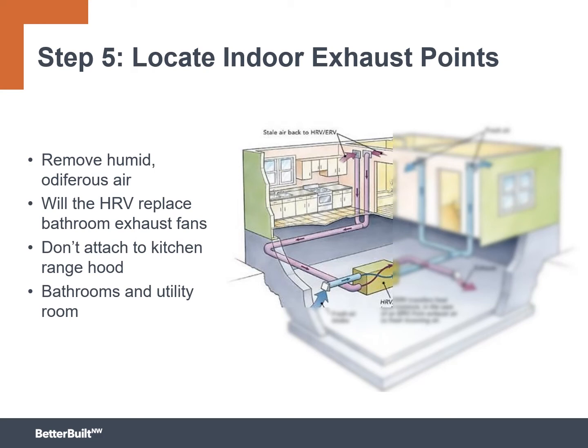But again, I keep using this word displace, right? So in this case, if we want to move, say, 10 or 15 CFM out of that bathroom more or less continuously, and by the way, there are some things like defrost cycles that have to happen with pieces of equipment where they temporarily maybe only recirculate air, so that's another consideration. But we can take a look and say the best case scenario might be we could put in a 70 CFM bathroom fan instead of a higher one. And that's going to meet 88% of the local exhaust requirement all by itself. And then the HRV exhaust will do the rest. So this may still give builders some savings, because you don't always need an 80, 90, or 100 CFM local exhaust fan. If you can get away with the 70 plus a small amount of continuous ventilation exhaust from your HRV, you're pretty well set up for success.